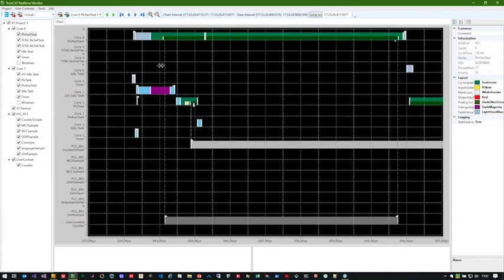Further on, you see directly that the IO idle task has a higher priority than the PLC task of the second core. For those of you who already know this, the IO idle task is used for the background communication, for example from the engineering environment to the target system, but also for grabbing the information from the real-time monitor, and also for parameter communication between the different I/O terminals.